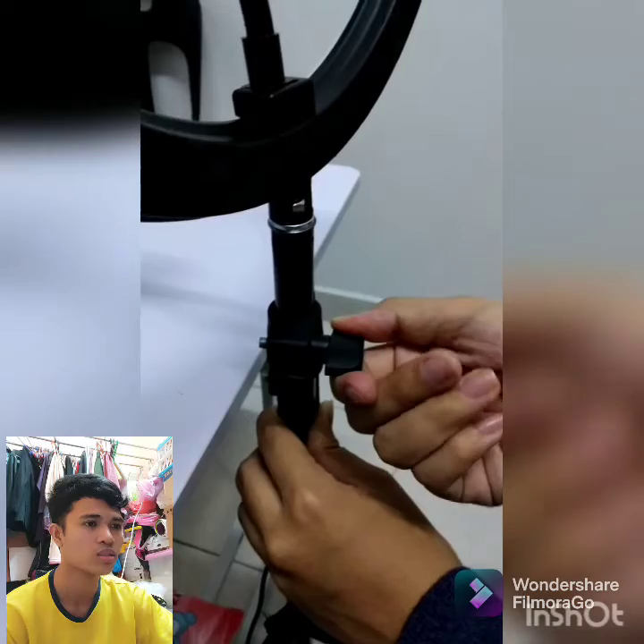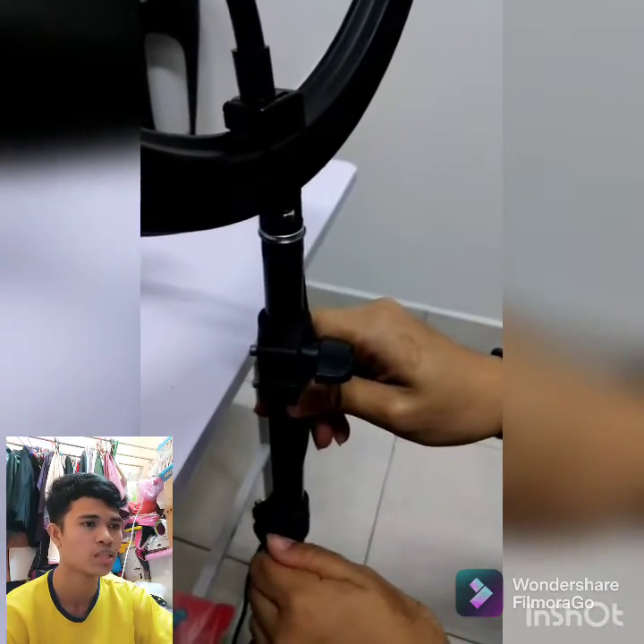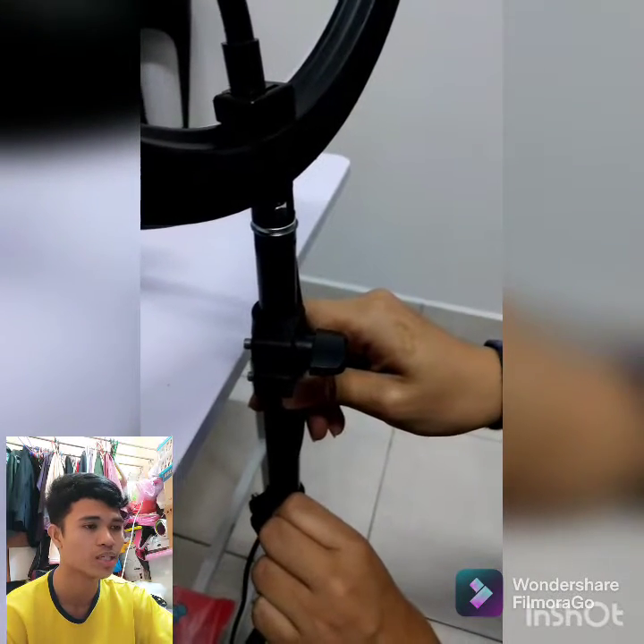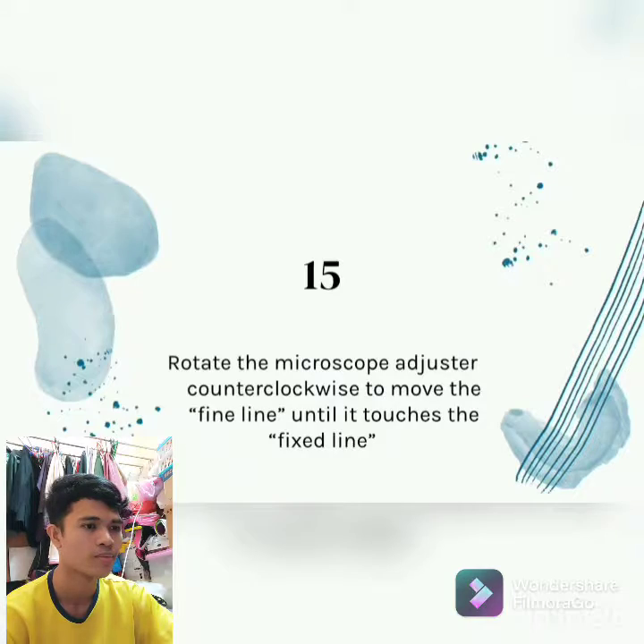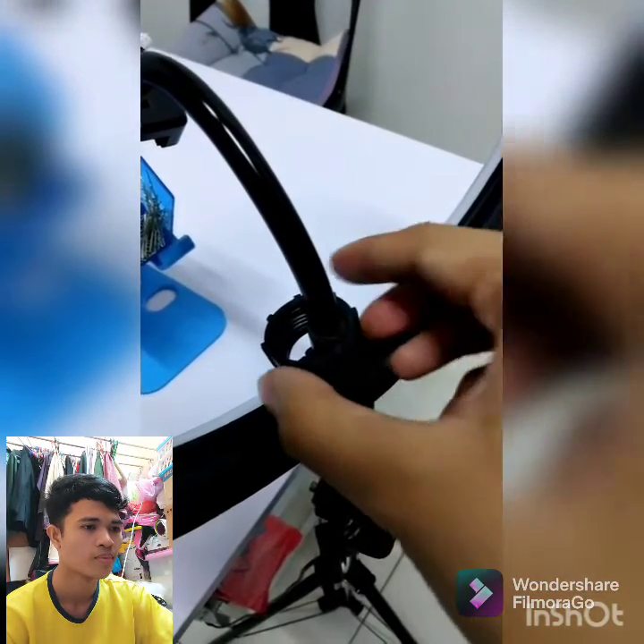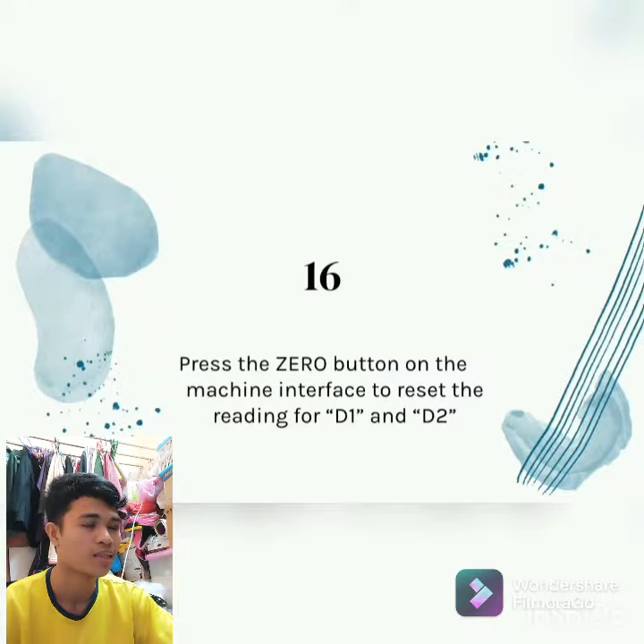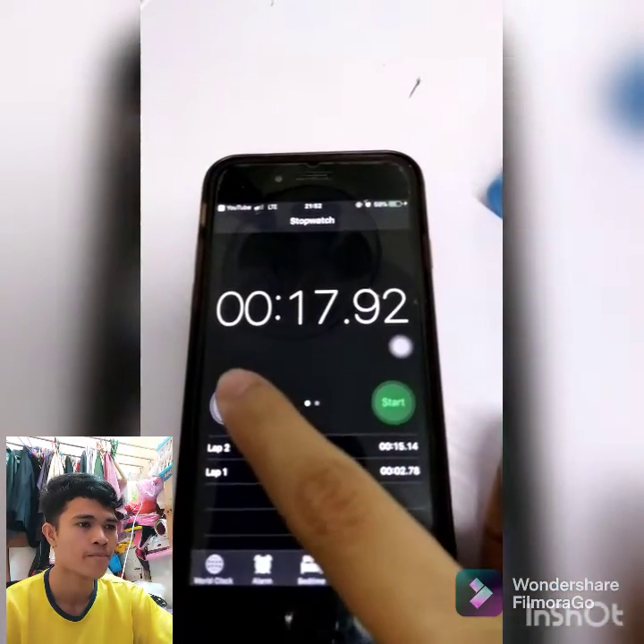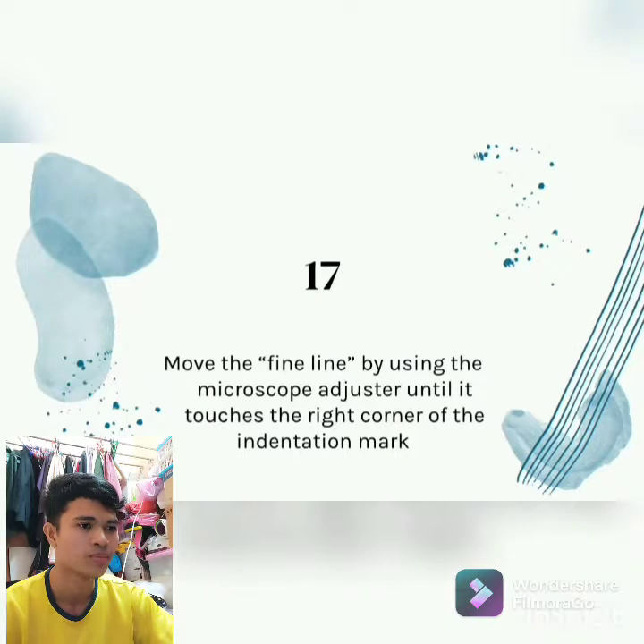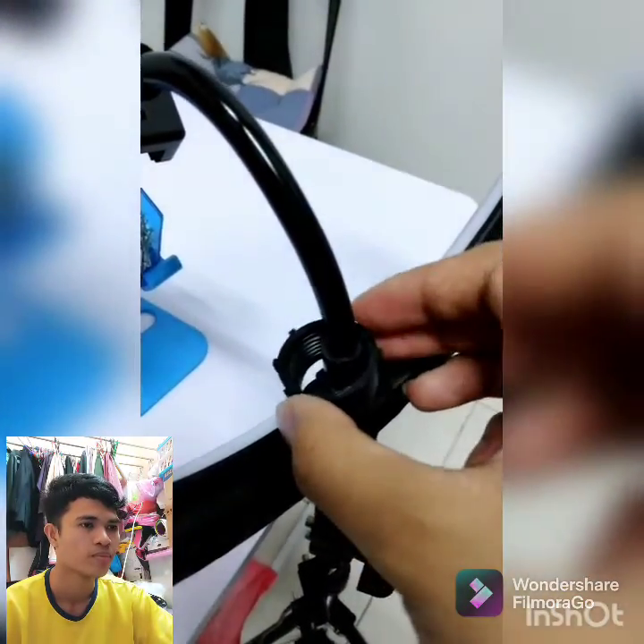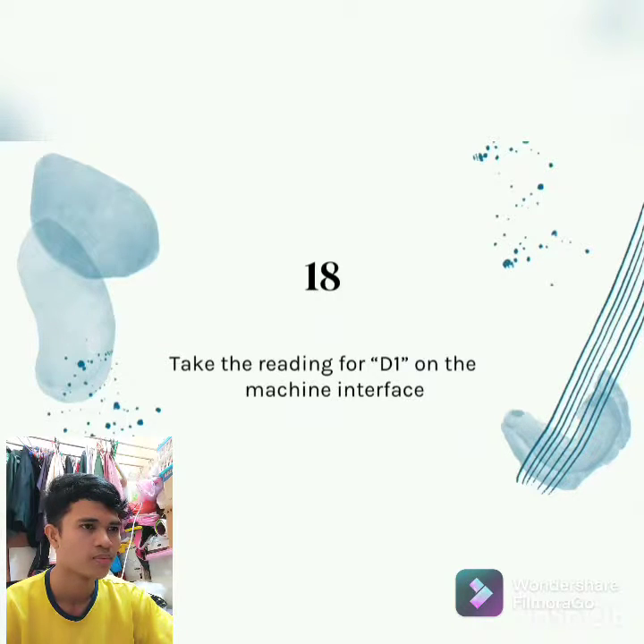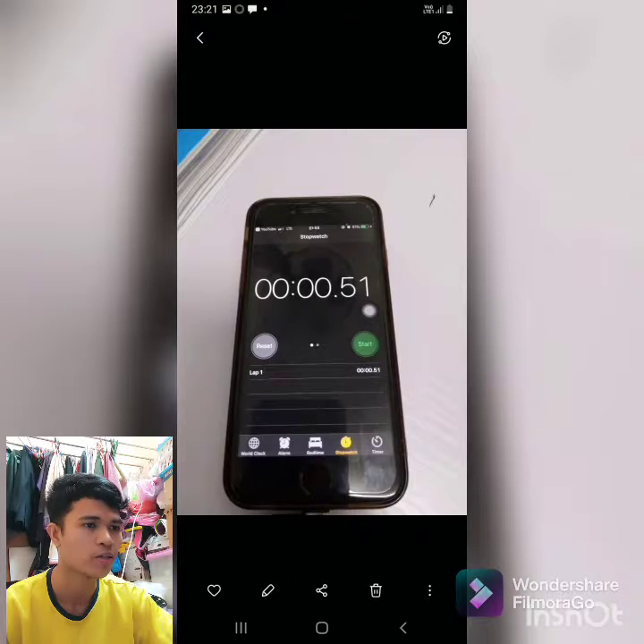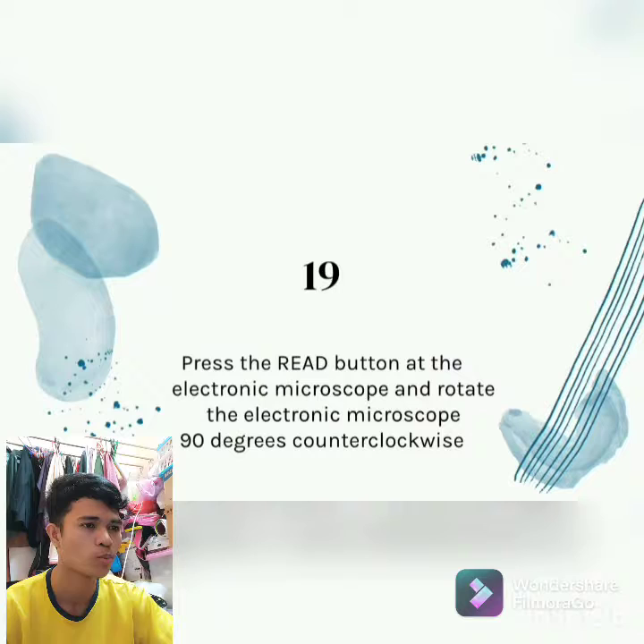Then press the 0 button on the machine's interface to reset the reading for D1 and also D2. The next step is to move the fine line by using the microscope adjuster until it touches the right corner of the indentation mark. Then take the reading for D1 on the machine's interface. After that, press the read button at the electronic microscope and rotate the electronic microscope 90 degrees counterclockwise.